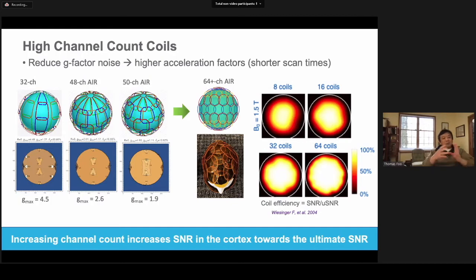Increasing the number of coil elements doesn't do much for the SNR in the center, as indicated from what Florian Wiesinger showed. However, as you can see here, increasing the number of channels would increase the SNR in the periphery of the region of the head, which is essentially where we want to increase the SNR, which is in the cortical region.